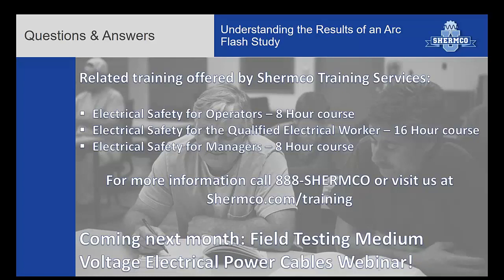Now, a gentleman did make a good comment. He believes that the new National Electrical Code requires an arc study. I do recall reference to that. I'm not sure if it's required or recommended, but I do know that in the new NEC, an arc study is brought up. And in the 2018 70E, they are also now stating that if you did have an arc study done, within time periods not to exceed every 5 years, you need to review it and make sure that it still holds and that nothing has changed.